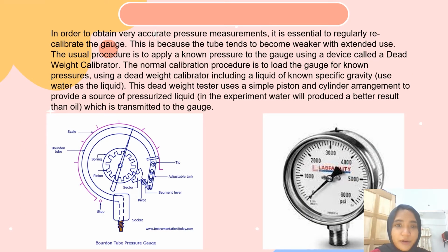In order to obtain very accurate pressure measurements, it is essential to regularly recalibrate the gauge. This is because the tube tends to become weaker with extended use. The usual procedure is to apply a known pressure to the gauge using a device called a dead weight calibrator. The normal calibration procedure is to load the gauge with a known pressure using a dead weight calibrator, including a liquid of known specific gravity. Use water as the liquid. This dead weight tester uses a simple piston and cylinder arrangement to provide a source of pressurized liquid. In the experiment, water will produce a better result than oil, and is transmitted to the gauge. That's all from me.